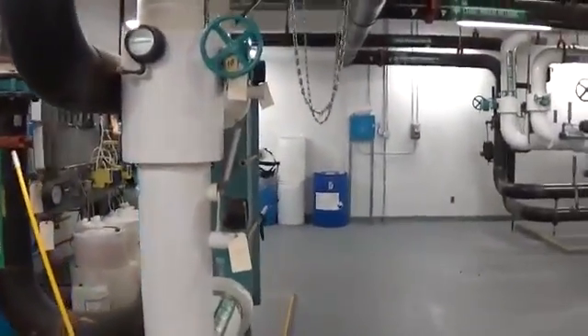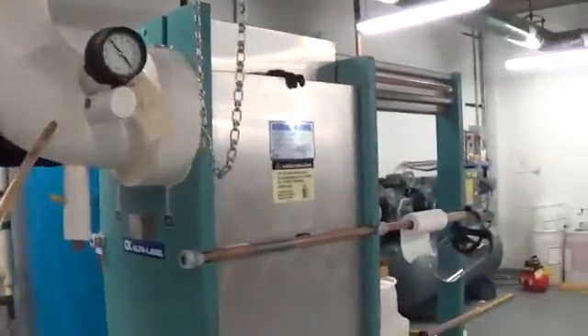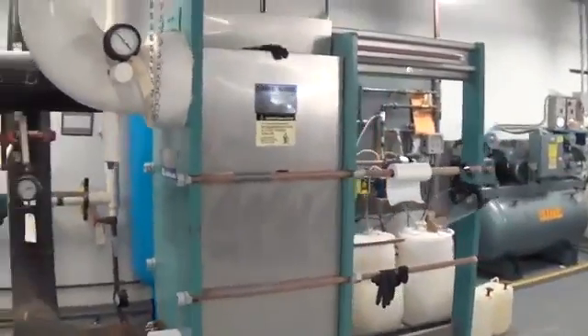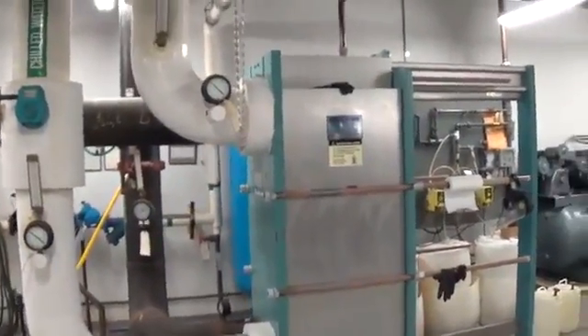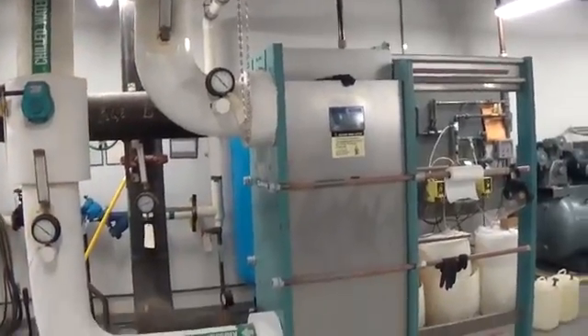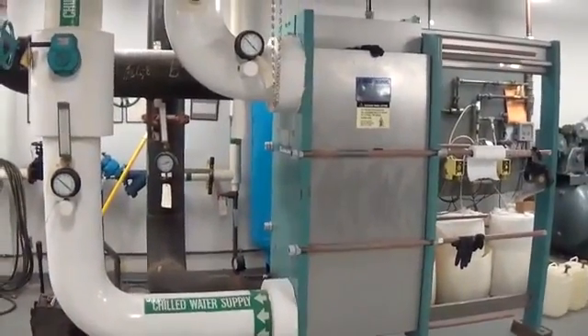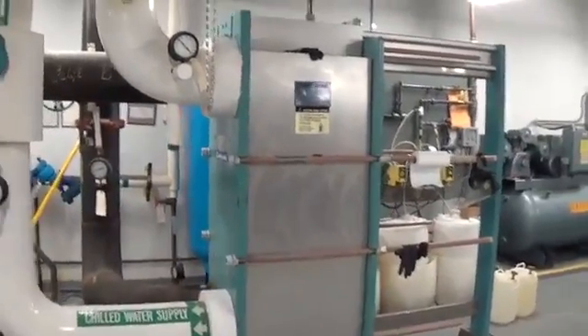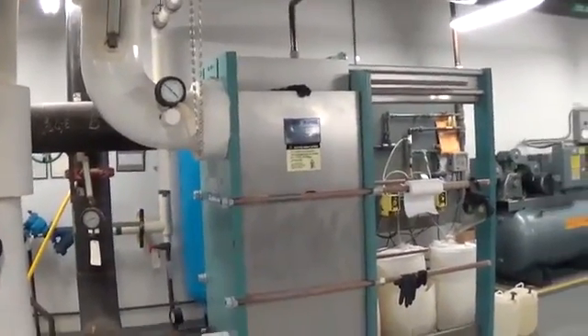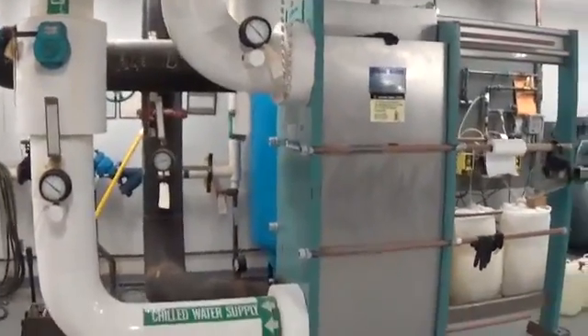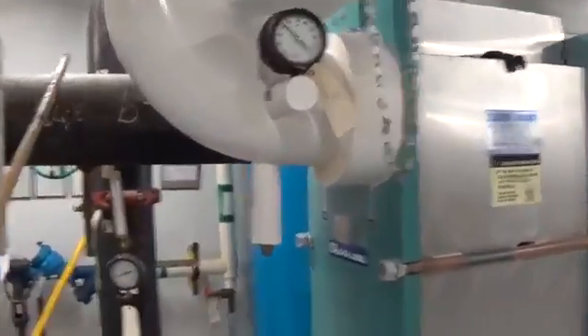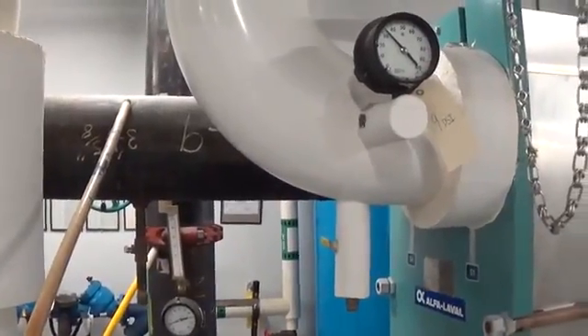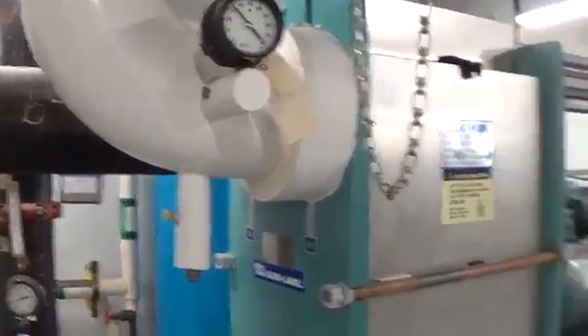Now this building also has a nice feature with what's called an economizer, and that's what we're looking at now, or a heat exchanger. And what this piece of equipment does, through some sophisticated automation, which is located in the building in the chief building engineer's office, it watches a condition called enthalpy.